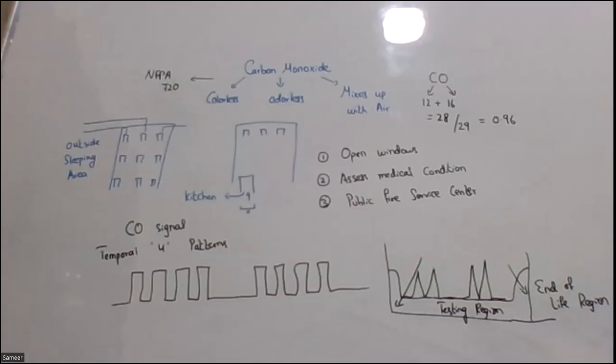Similarly, it goes for the fire alarm systems. In a similar situation we identify the number of faults per year and how much investment we have to make per year. Usually the manufacturer does not provide 5 years. They usually provide 1 year of maintenance, 1 year of component failure coverage, because if they provide long term, it's not beneficial for them. And electrical components tend to get short, because there could be transient signals coming from AC or DC that can affect the electrical components. So for that purpose, we usually make the bathtub curve.